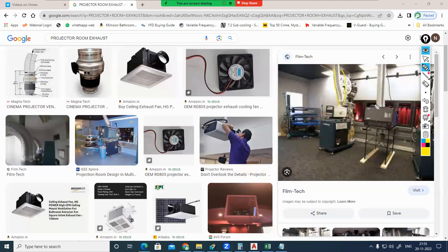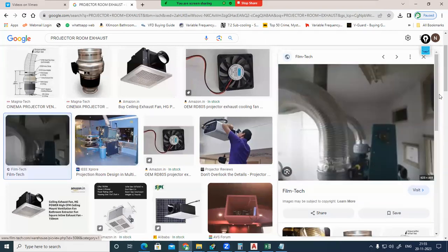Correct. This is an exhaust fan. The inbuilt exhaust fan within the projector will not have that much static pressure to suck the air and deliver it outside. So in between, the duct system will have fans proposed. Those fans are called inline ducted fans. In between the duct branch we will propose it, or on the roof side we might propose a roof mounted fan. Anyway, whatever it may be, one fan will be there. For example, this one is an inline ducted fan. See, in between the duct branches, we connect a fan.